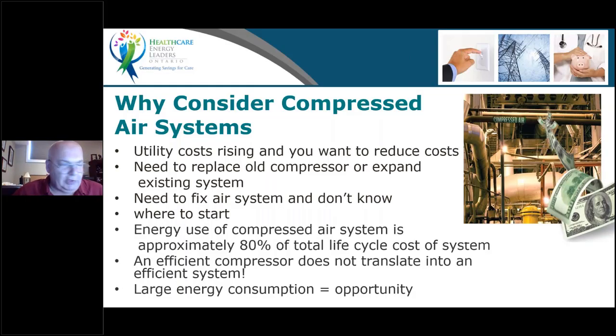So when we look at compressed air and the opportunities, why do we look at compressed air? It's one of the major consumers of electrical power to run motors. Utility costs are on the rise. A lot of customers are looking at upgrading compressors or expanding an existing system. They don't know how to go about fixing it other than purchasing a new compressor. An efficient compressor purchase does not necessarily mean that the system is efficient overall.